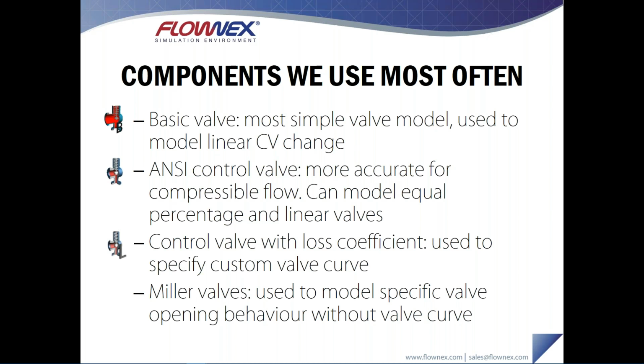If you're looking to account for choking effects or model compressible flows better, then I'd suggest the ANSI control valve. It's going to be more accurate for compressible flow. It also does choking a lot better. You can model different types of valve curves. So you can model an equal percentage curve, a linear curve. You can even specify an ANSI chart to capture the exact performance of your valve.